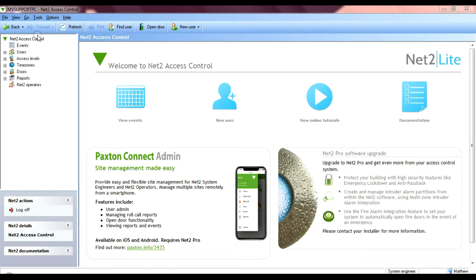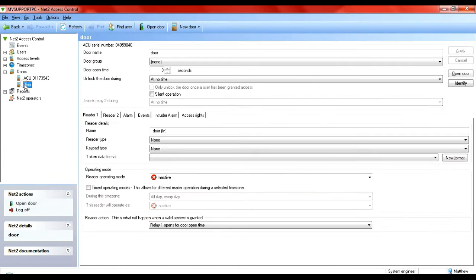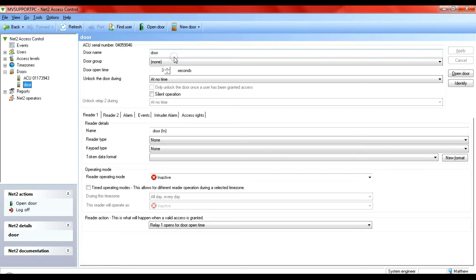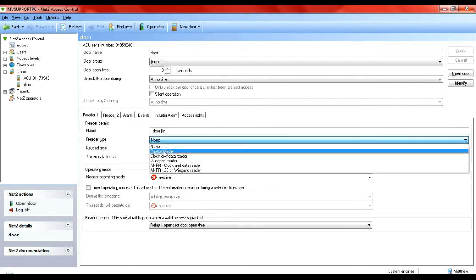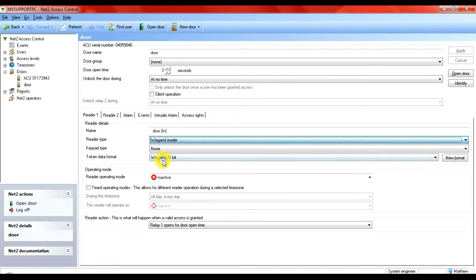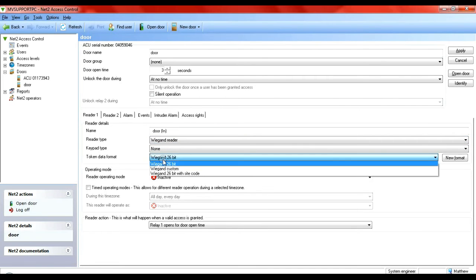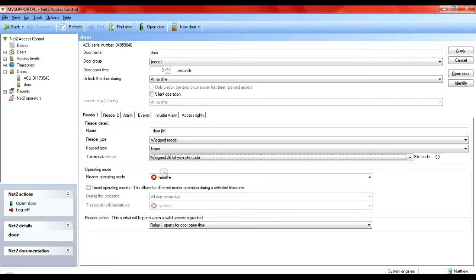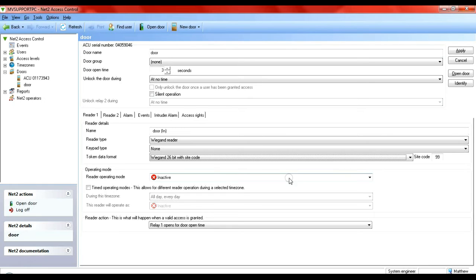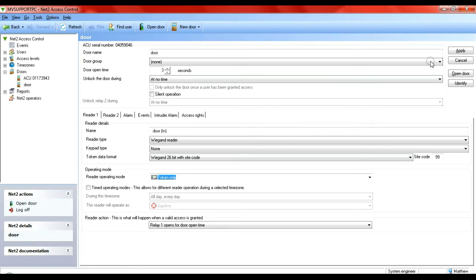Okay so here we are in Net2. Let's go to doors. Let's go to this one here, this is my test door. I've just added it in the standard way and gave it its name. What we have to do is change the reader type from the factory setting from none to Wiegand, it's 26 bit. But if you remember I said it's important you remember that site code, because this is where it becomes useful to use that feature. Now as you can see, the standard site code in Net2 is 99. You can change this number to any number you like, but I've done it to 99 for this example to show you how to do this. Read the operating mode, we're going to have it token only, and click apply. And that sends the information through to the controller.